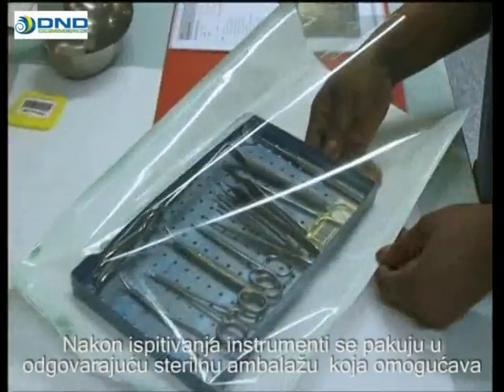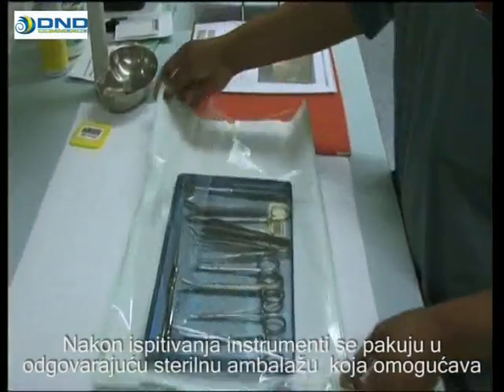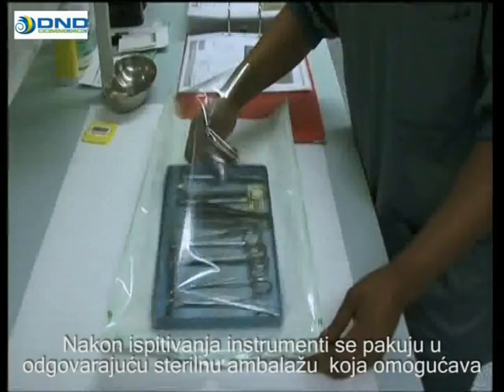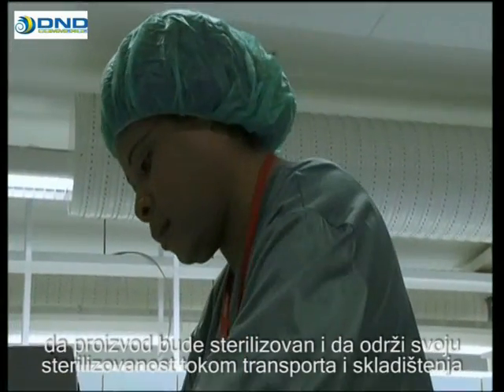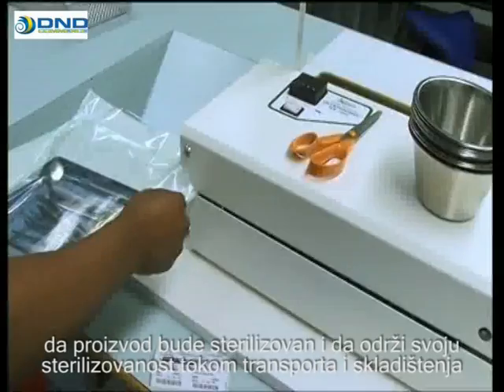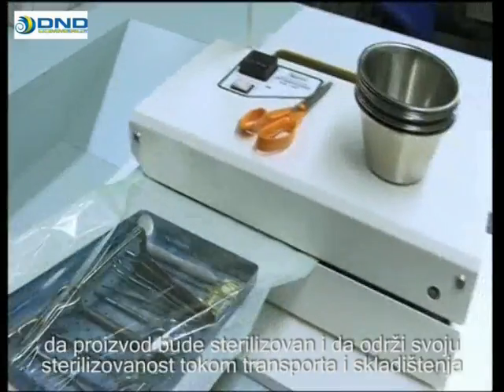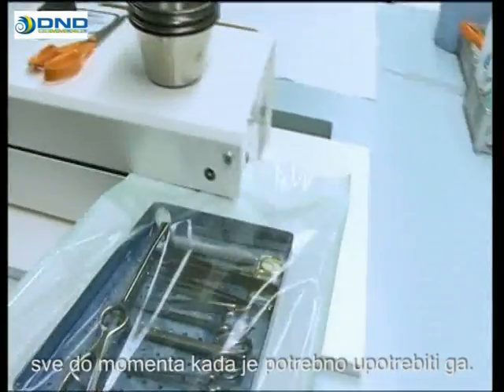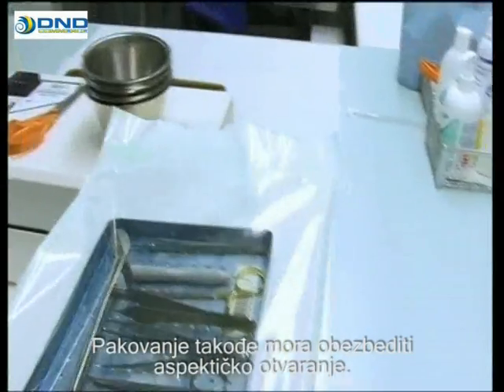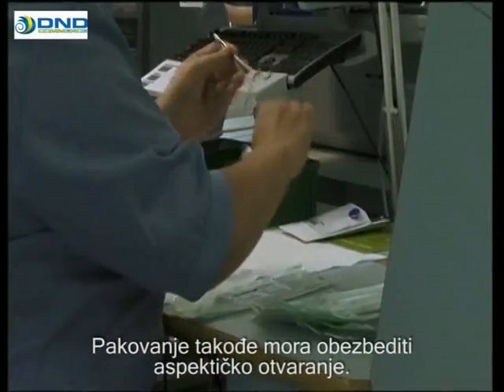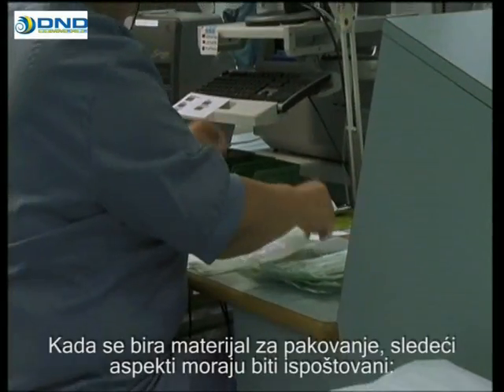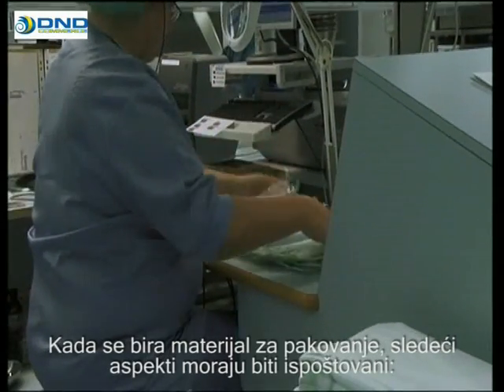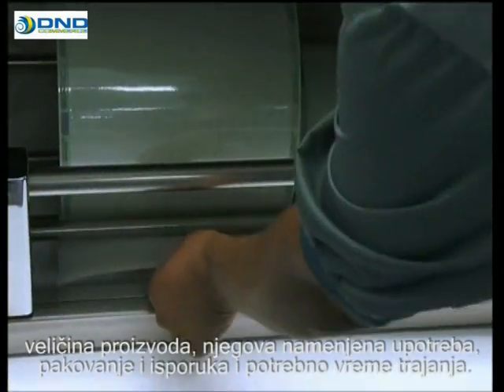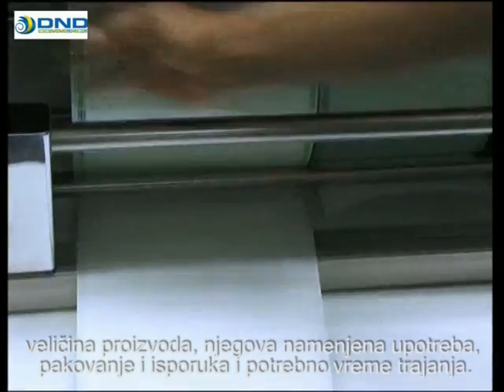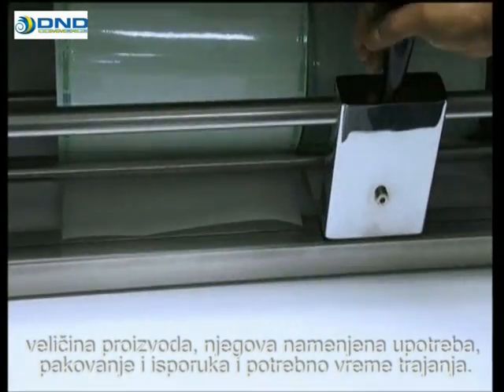After they have been inspected, the instruments are packed in the appropriate sterilization packaging, which enables the product to be sterilized and to maintain its sterility during transport and storage right up to the moment it is used. And the packaging must also allow aseptic opening at this point in time. When selecting the packaging material, the following aspects need to be considered: the size of the product, its intended application, packaging and shipping, and the required shelf life.